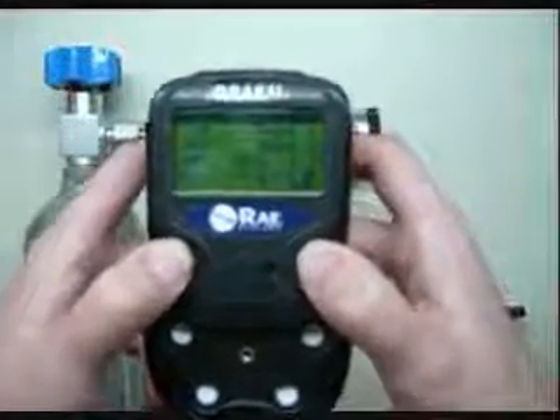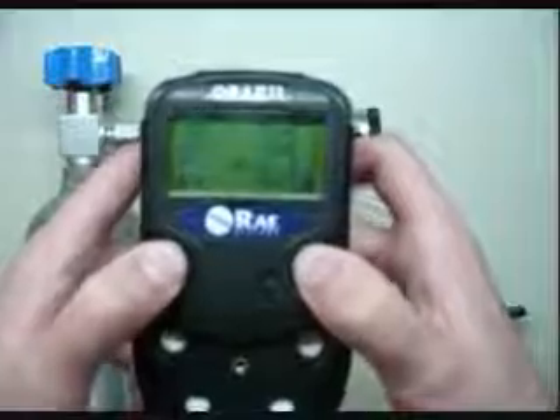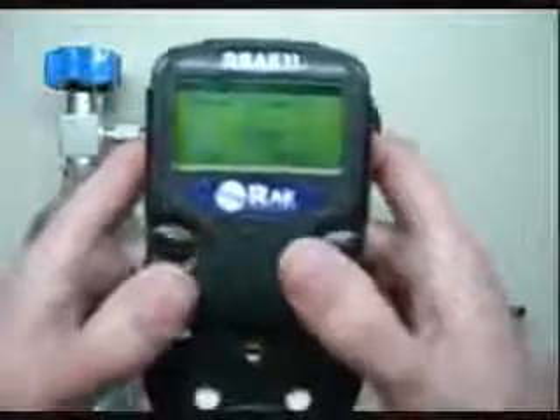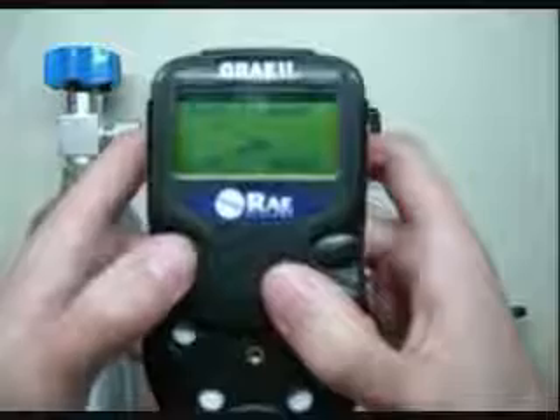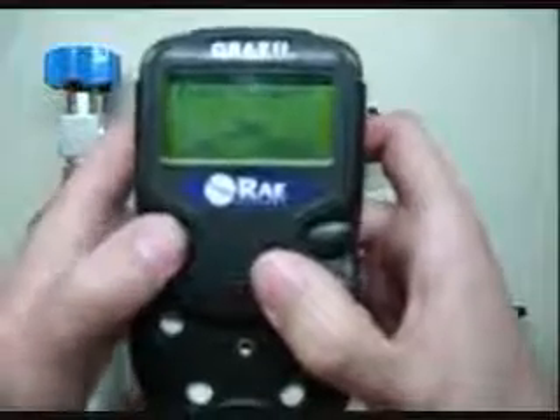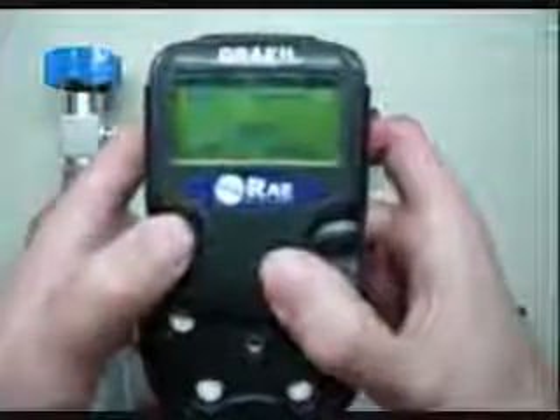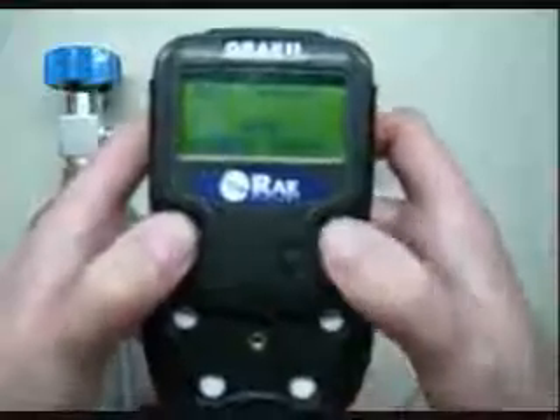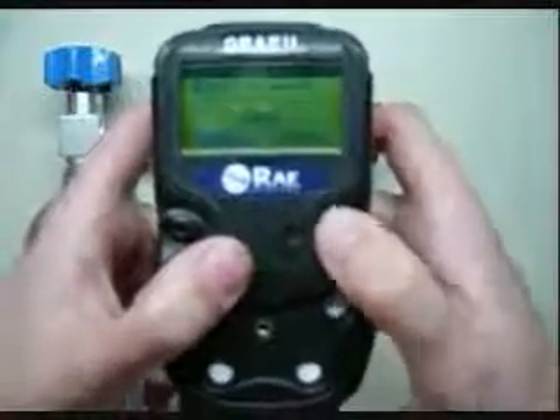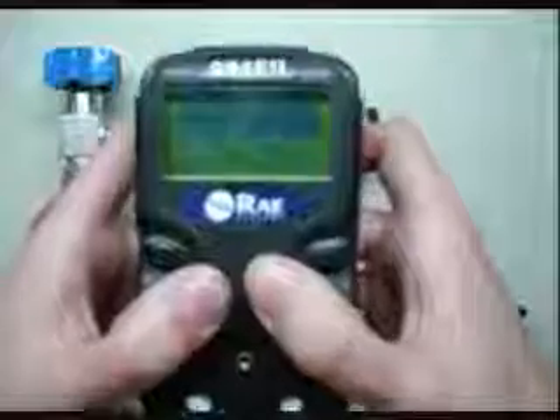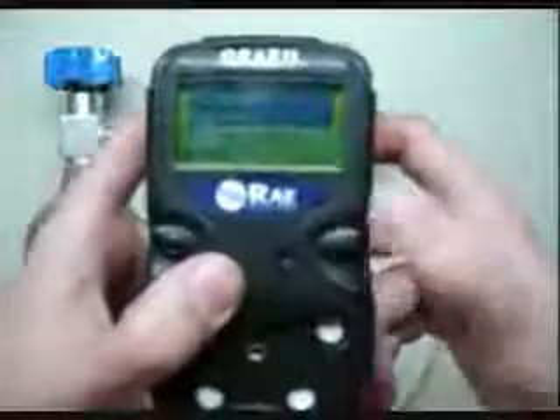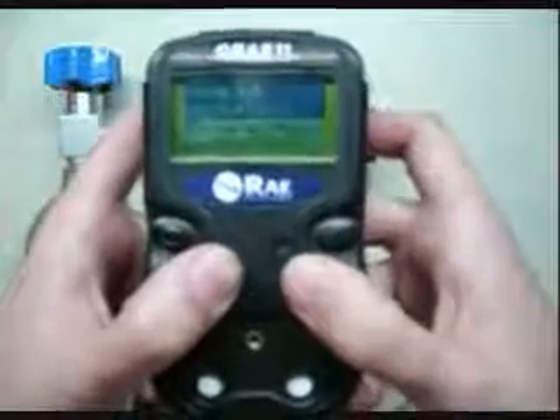Okay, in order to calibrate, we're going to take both buttons, press them together and hold them for about 5 seconds. It's going to come up asking for a password. For us, our password is 000. You might have your own. In order to skip forward, press the button 4 times, and then press yes on OK. It'll pause the data logger for you and ask if you want to calibrate.